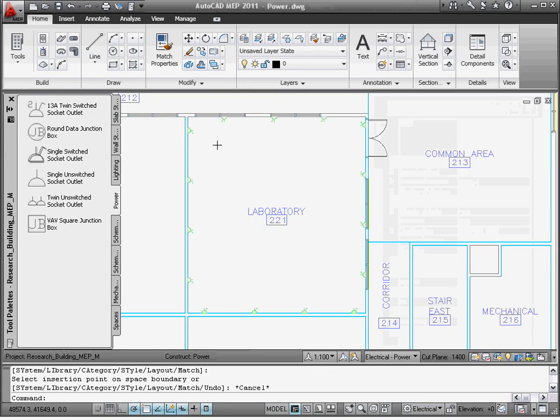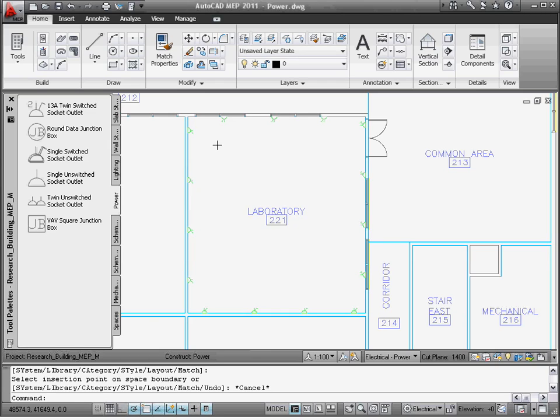Notice that Circuit Manager is warning me about the total load exceeding 80% of the defined rating. This is a major benefit as it provides instant feedback on the design. I can cancel the task or continue. In this case, I'll continue.